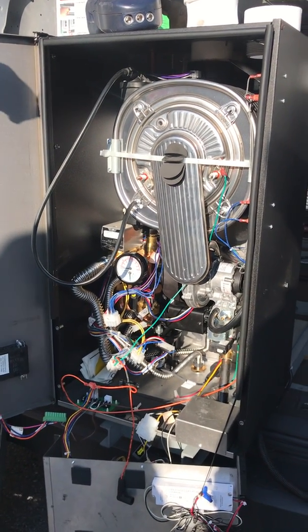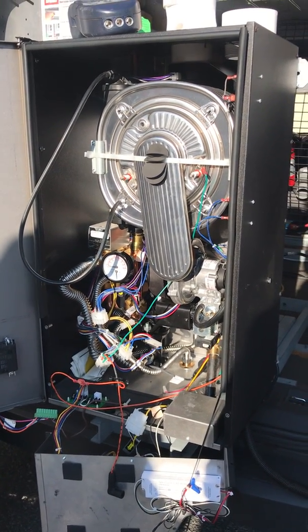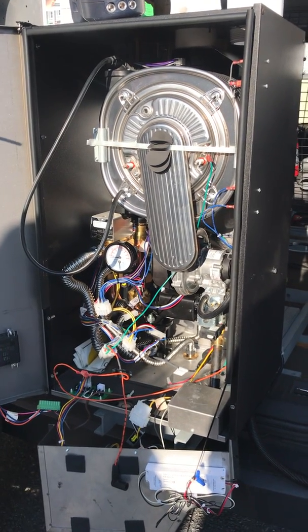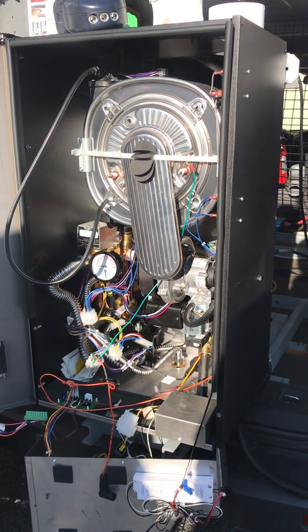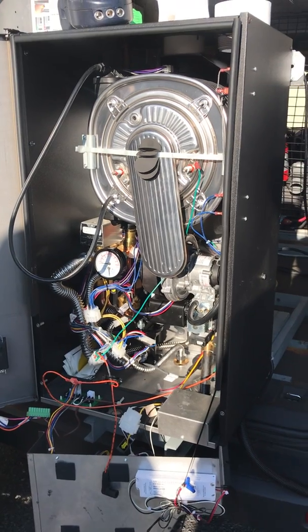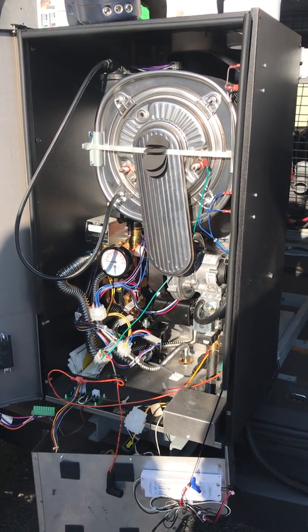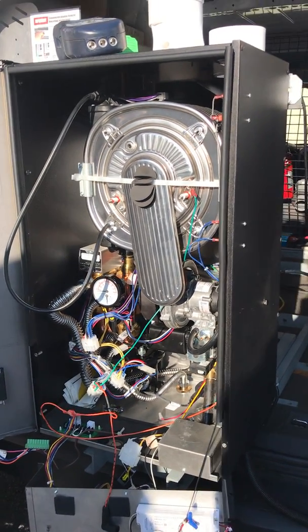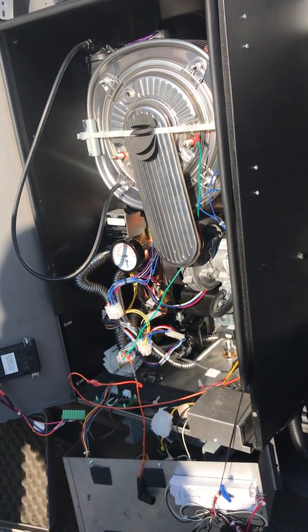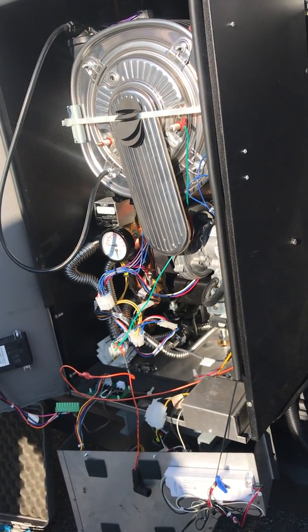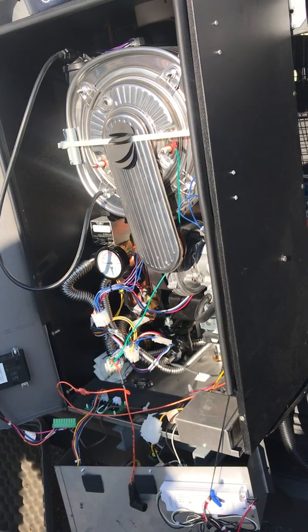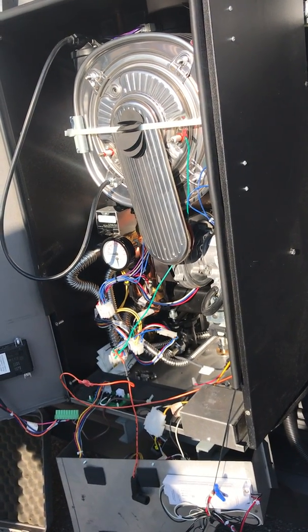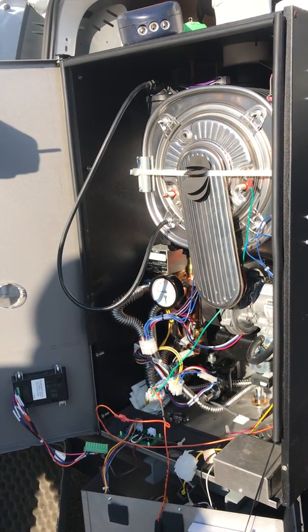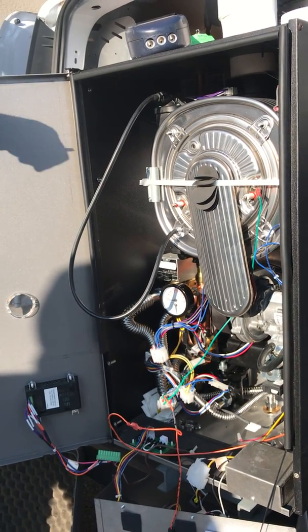I want to look at my flame signal, and I'll show you upstairs how you can see the flame signal. Okay. And there's some really neat things you can do for troubleshooting this, but the flame signal on this is really good. The minimum is 0.9, and the maximum, you'll probably get close to 30. So it's a big range. Yeah. We don't dual sense. It only senses through the flame rod. Some other manufacturers sense through the spark rod and the flame rod. We just sense through the flame rod.